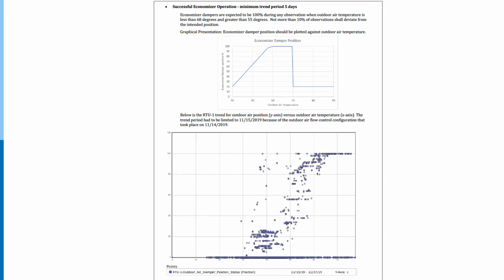The next one here is economizers. Economizers are actually a pretty old strategy. They've been around in HVAC as long as I've been around in HVAC, and we rely on them a lot, particularly in the mild climates, right? So if you look at the engineer's energy models, the economizer is supposed to be open every hour that it's supposed to be open, and then closed every hour that it's supposed to be closed. And so our acceptance criteria is that we would trend this for 5 days, and not more than 10% of the points should deviate from the intended position of the economizer.